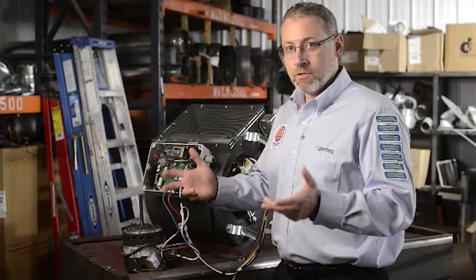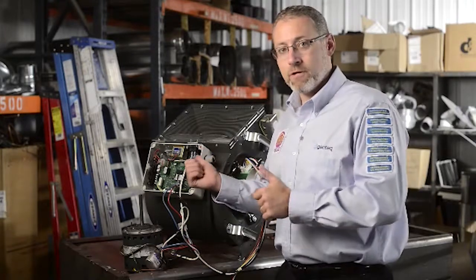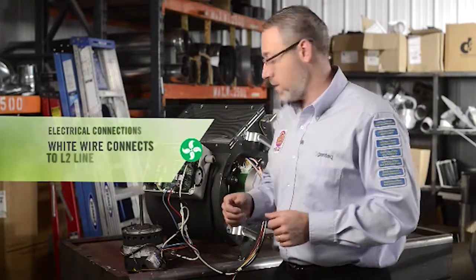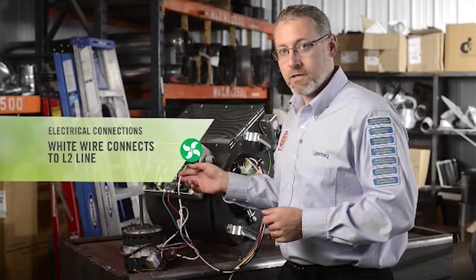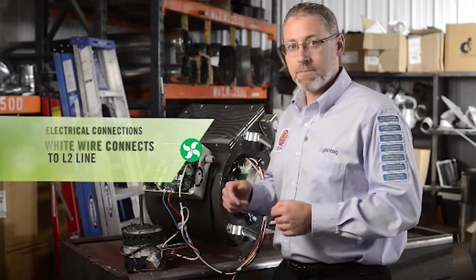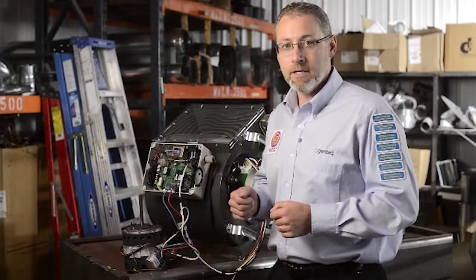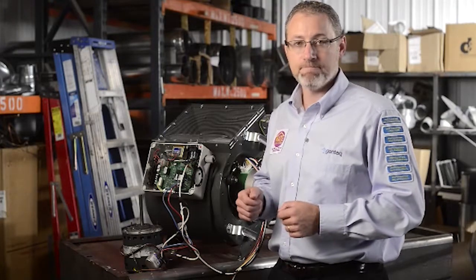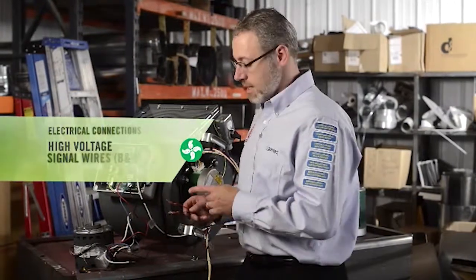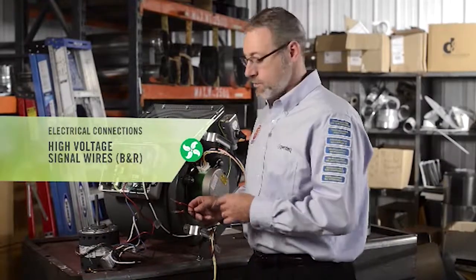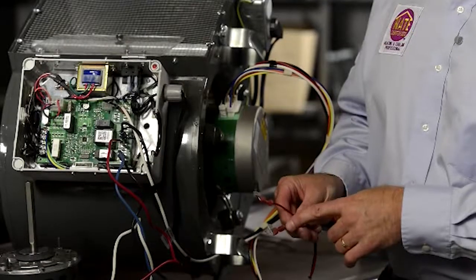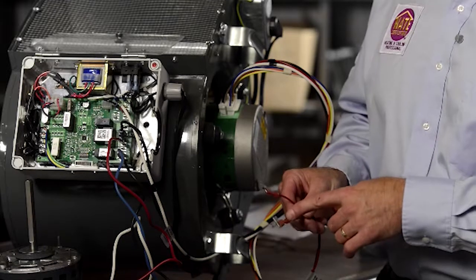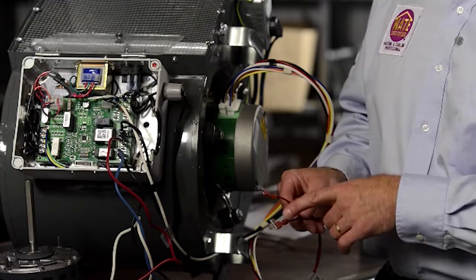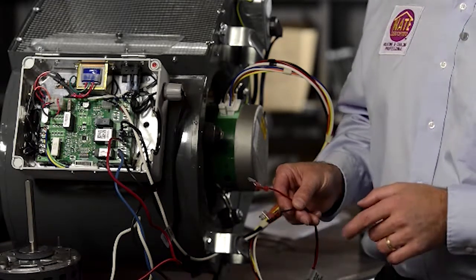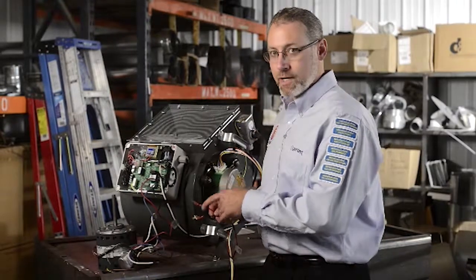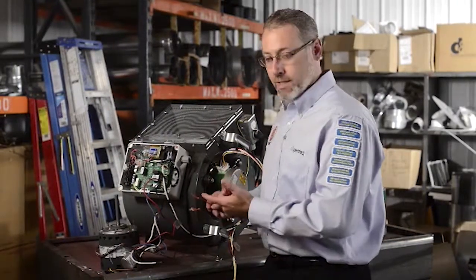our wiring. The only change we would make if this were a 230-volt air handler, package system, or furnace is our white wire, instead of connecting to a neutral tap, would actually be connecting to the L2 line of the HVAC system power supply. Next, we're going to talk about connecting the high voltage signal wires to the HVAC system. You'll notice that they come prepared with a 1/4-inch female spade terminal on both wires and 1/4-inch Y adapters. This is going to make connecting these two wires to your HVAC system quick and easy.